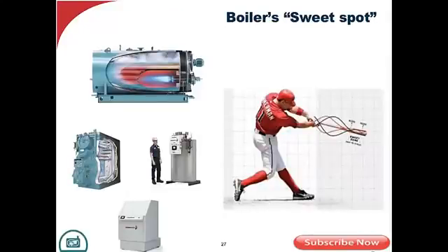Now also, let's talk about the boiler's sweet spot. We've got a number of boilers that we manufacture, various types. They're configured with various controls and burners and so on and so forth. But every one of those is unique. Each one of those types has its own signature based on horsepower, fuel, burner, and so on. It's got its own sweet spot. And that becomes very, very important when we understand that particular boiler. We understand the load so that I can select the proper boiler to handle that particular load so it's operating in its sweet spot most of the time.